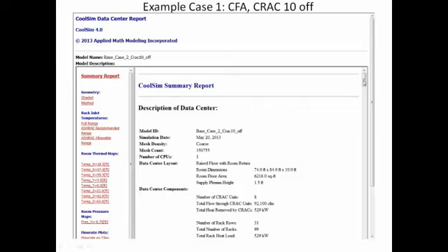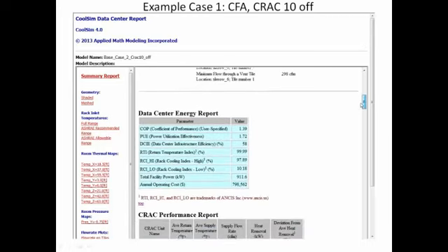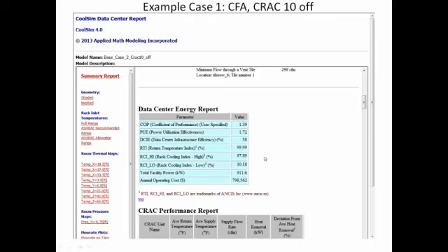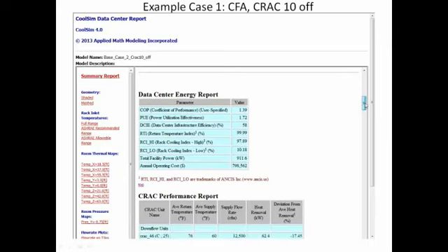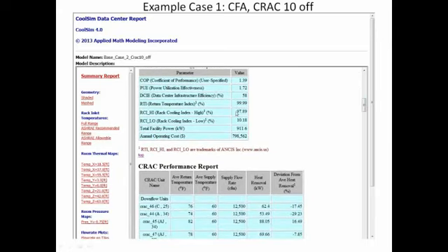So let's take a look at this one again. We'll scoot right down to the energy report. Now here, what's interesting, Magnus, look, we got to 99% on our RTI. Now that's because in this one, I shut off one of the 30-ton units, and that's got a flow rate of 17,000. So I'm bringing these two things together. What is interesting here as well is that my RCI high went to 97%. It improved a little bit over the last run, and the low came up.